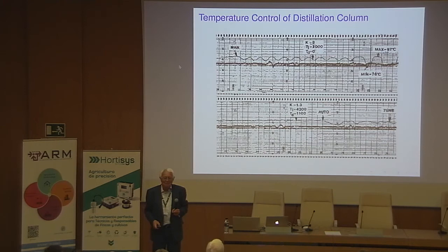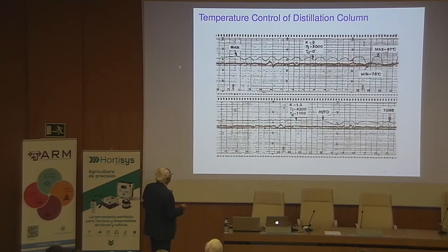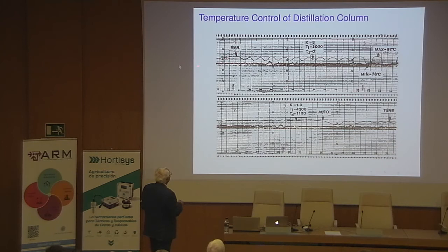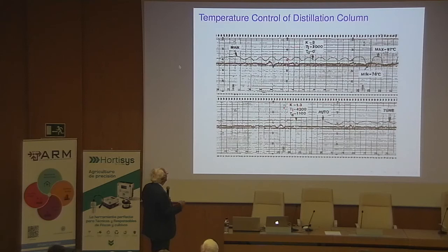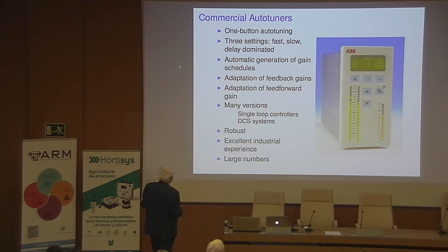People were enthusiastic. They came and said they had a process they'd never been able to control. We connected the auto-tuner: the system had an oscillation with no derivative action, gain of 8 and integral time of 2000. We switched to manual to stop the oscillation, then pushed the tuning button at 2 o'clock in the afternoon. From 2 o'clock to 8 o'clock we waited — measuring hysteresis, developing the relay oscillation. At 8 o'clock it finished, went automatic, reduced gain, and introduced a heavy derivative action. A nice example of what a relay auto-tuner can do.